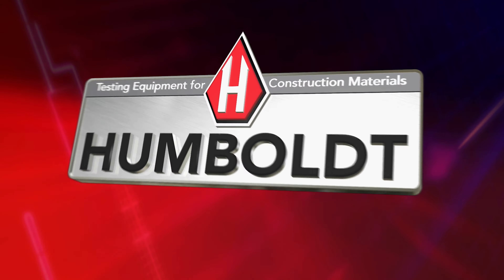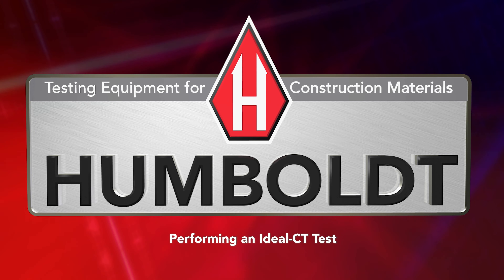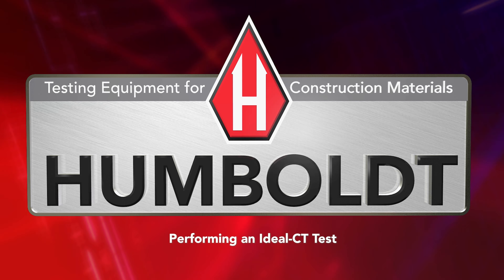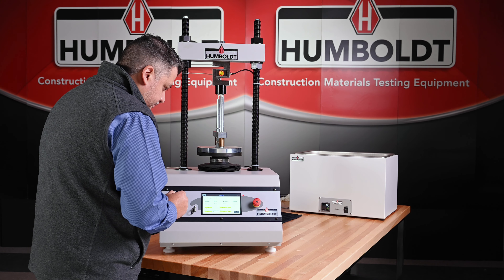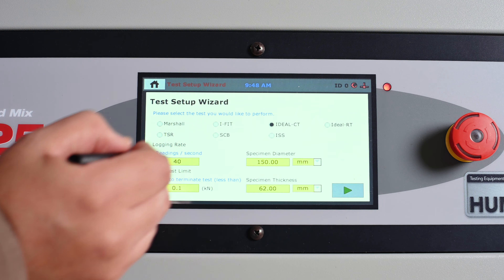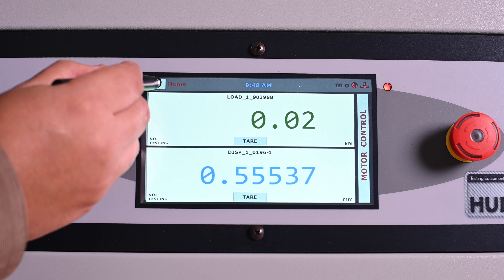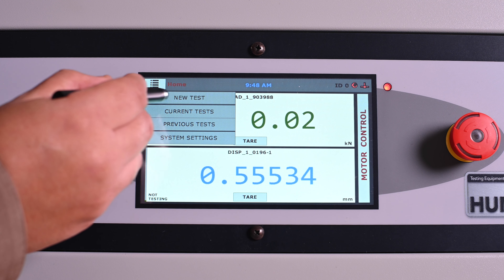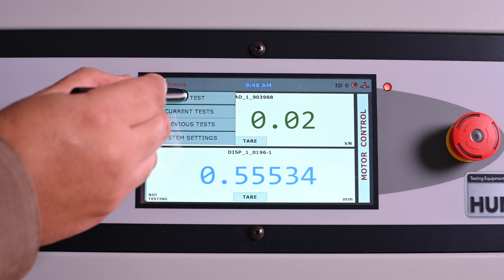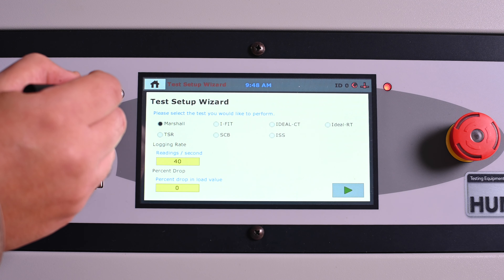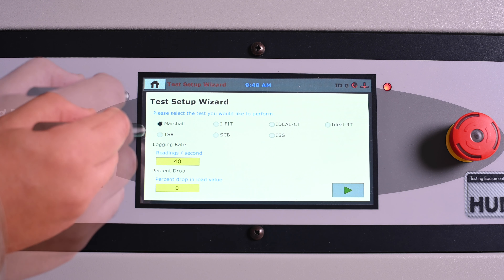How to perform an IDEAL CT test with the HM5125A. Humboldt's balanced mix design load frame makes IDEAL CT testing simple and easy. To begin a test, press the home button, which displays a drop-down menu. Select New Test. The test selection screen will appear on the display. Select IDEAL CT.